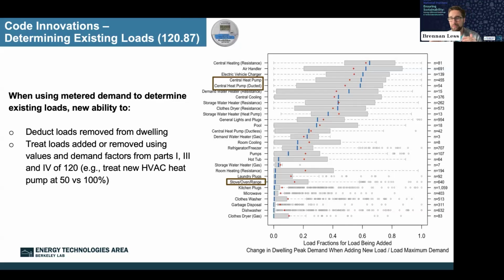The problem is that the current section in the code, 120.87, a lot of folks interpret as meaning that when you add a new load, you have to add it at 100% of the nameplate rating. If you're trying to add a new electric cooker, that's 12 kW. So if you look back at the average demand from the first slide, around 11 kW, you add that 12 kW load and you're at capacity - that's when you need to do panel and service upsizing.